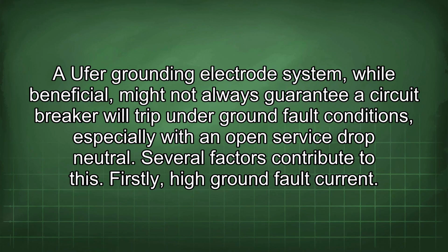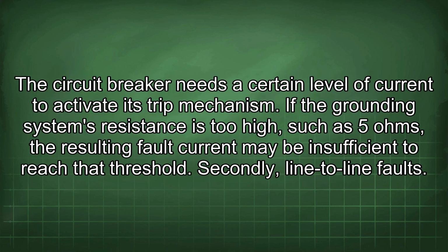A Ufer grounding electrode system, while beneficial, might not always guarantee a circuit breaker will trip under ground fault conditions, especially with an open service drop neutral. Several factors contribute to this. Firstly, high ground fault current. The circuit breaker needs a certain level of current to activate its trip mechanism. If the grounding system's resistance is too high, such as 5 ohms, the resulting fault current may be insufficient to reach that threshold. Secondly, line-to-line faults.